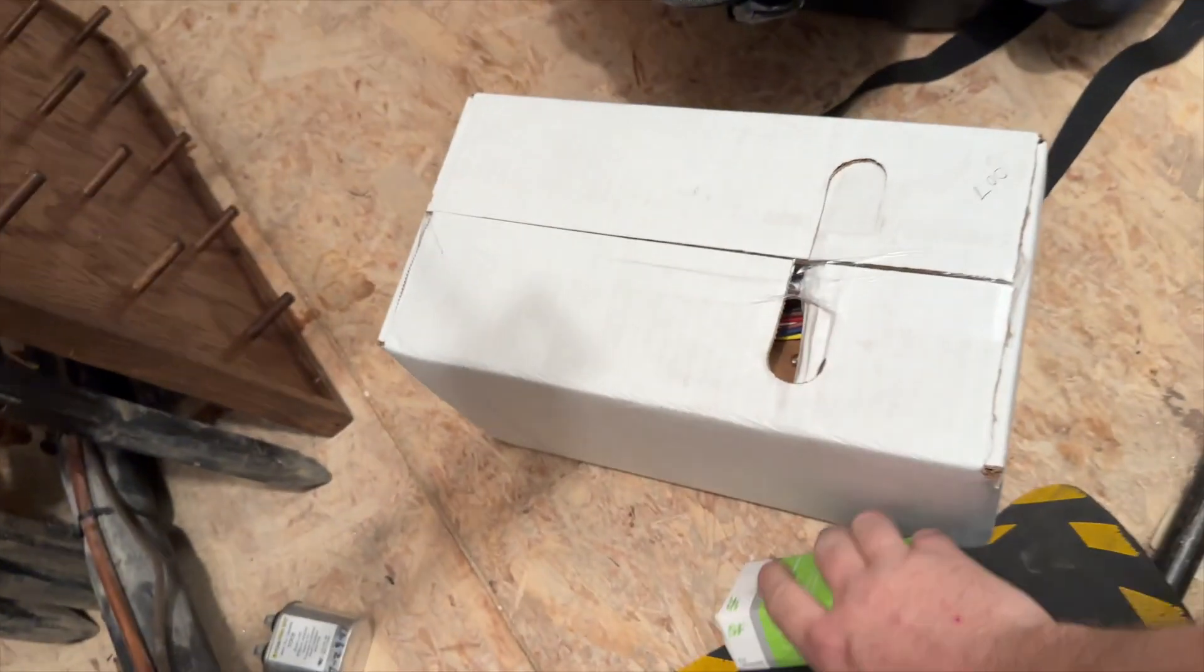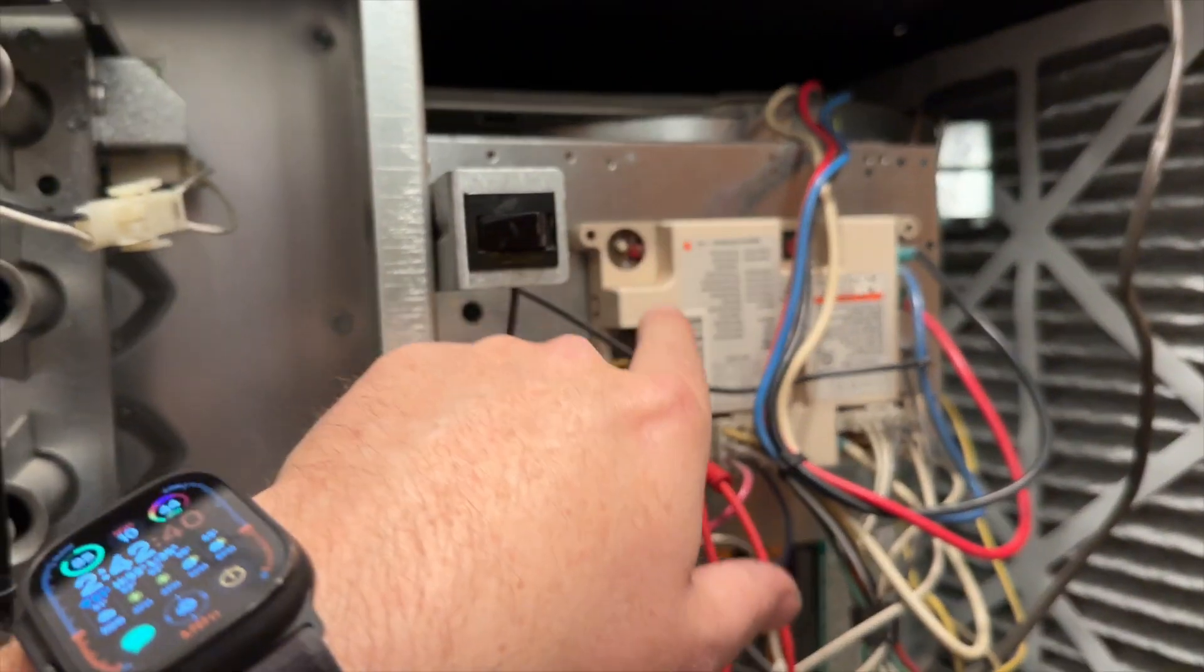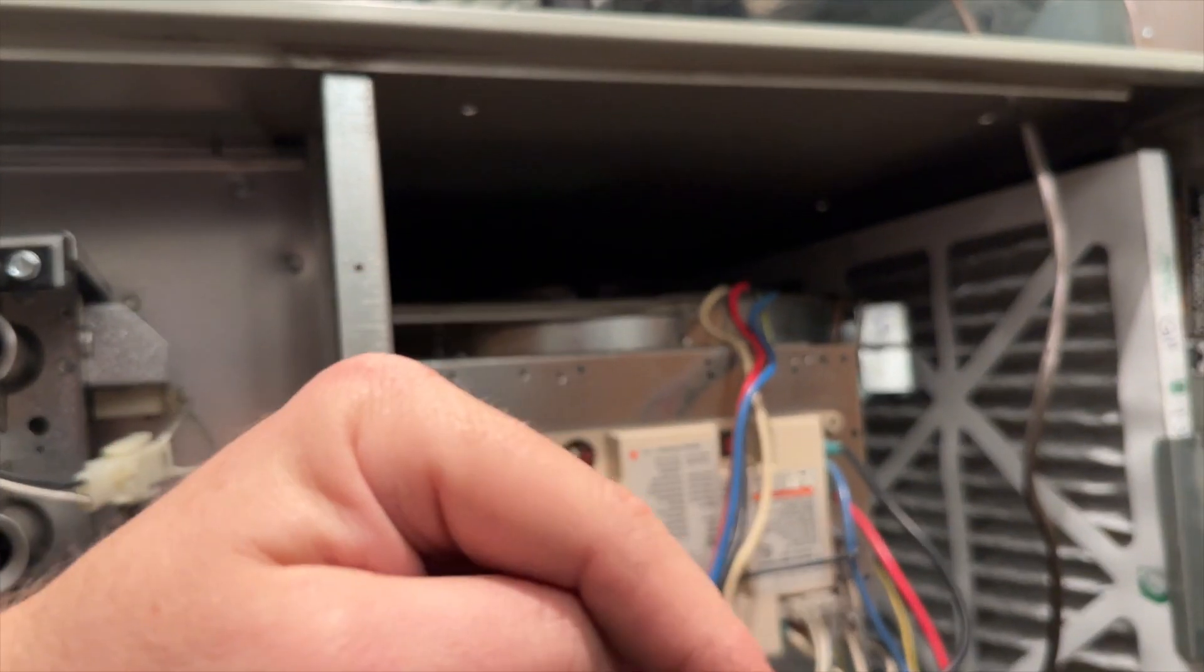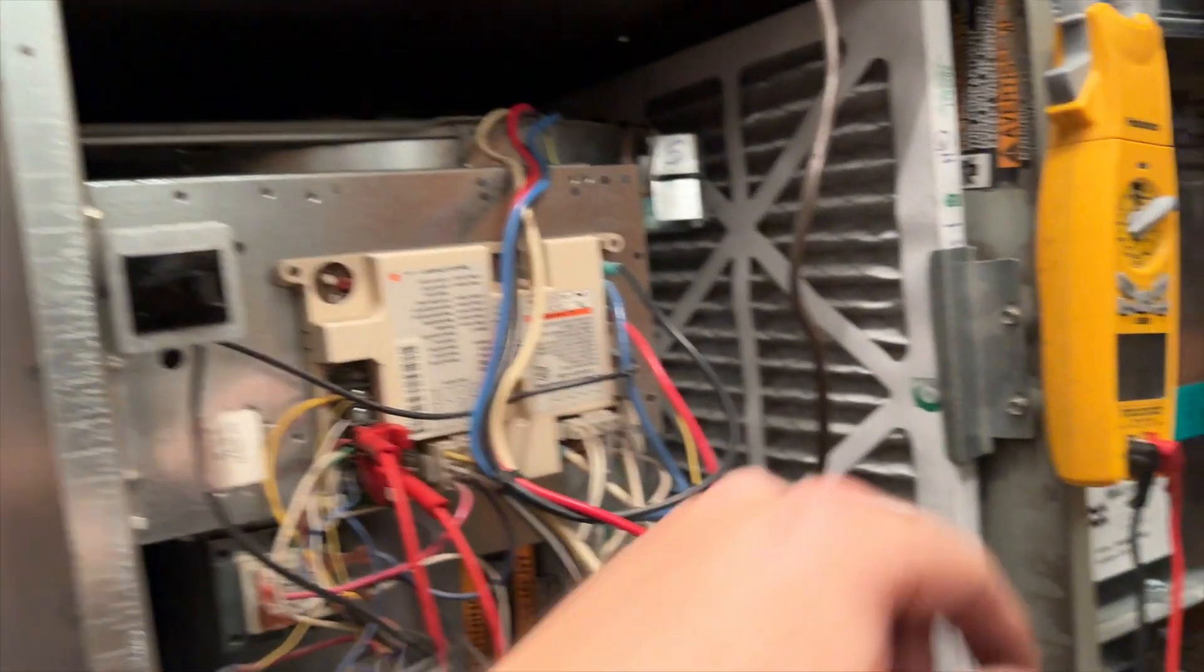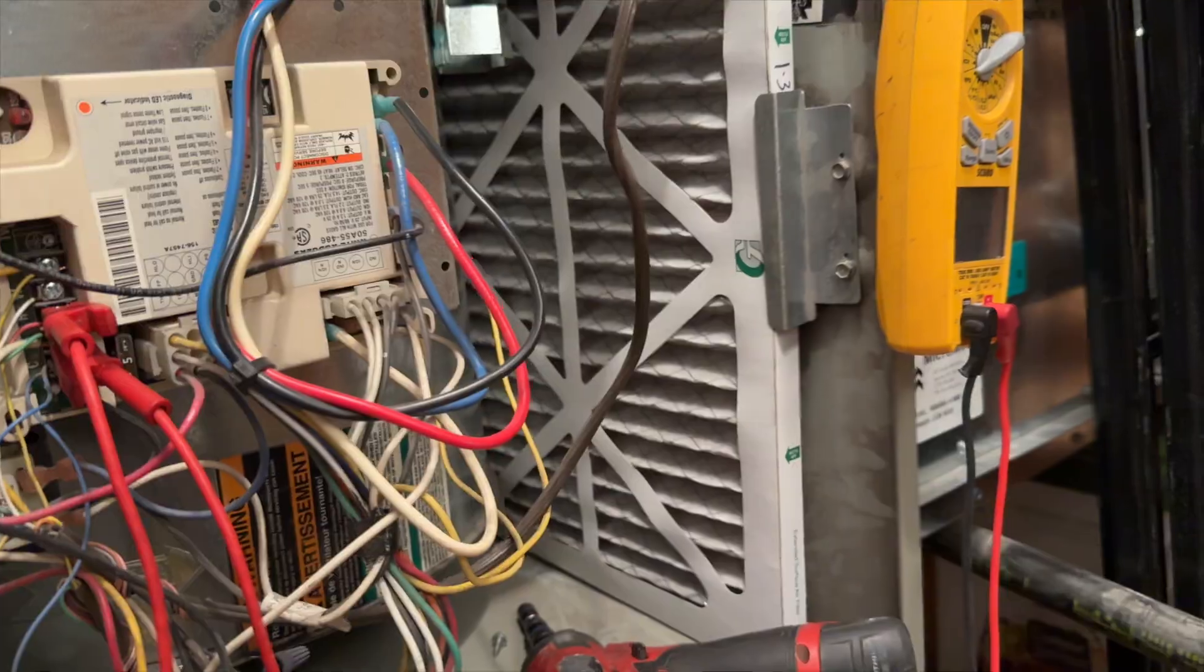We got our OEM motor here, came with the run cap, so we'll go ahead and replace that. We need to take the board out, blower assembly out, the motor out, new motor and run cap, put it all back together. So start by taking out the filter. Filter is not that dirty, just changed in January.